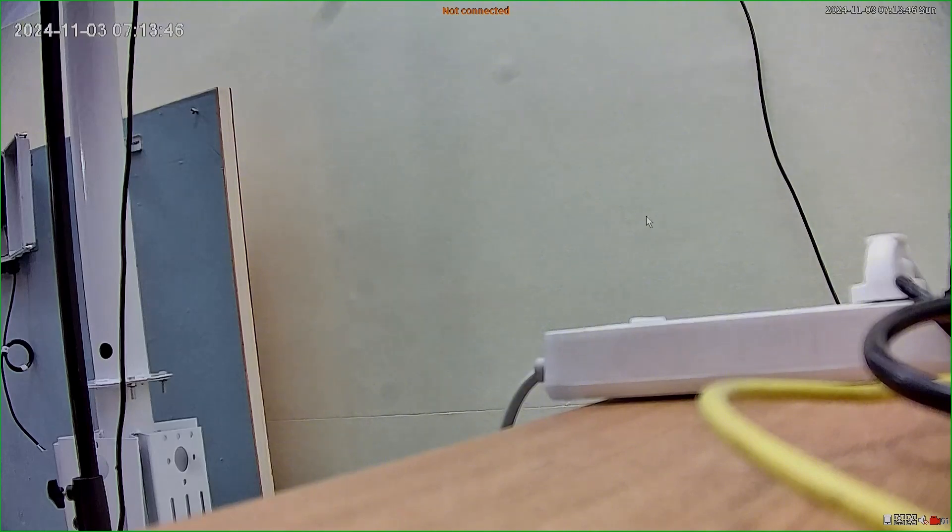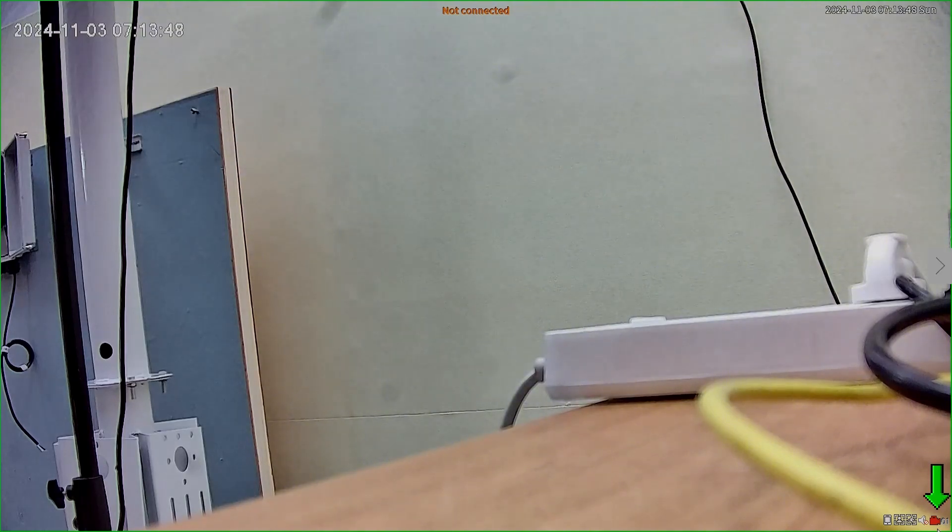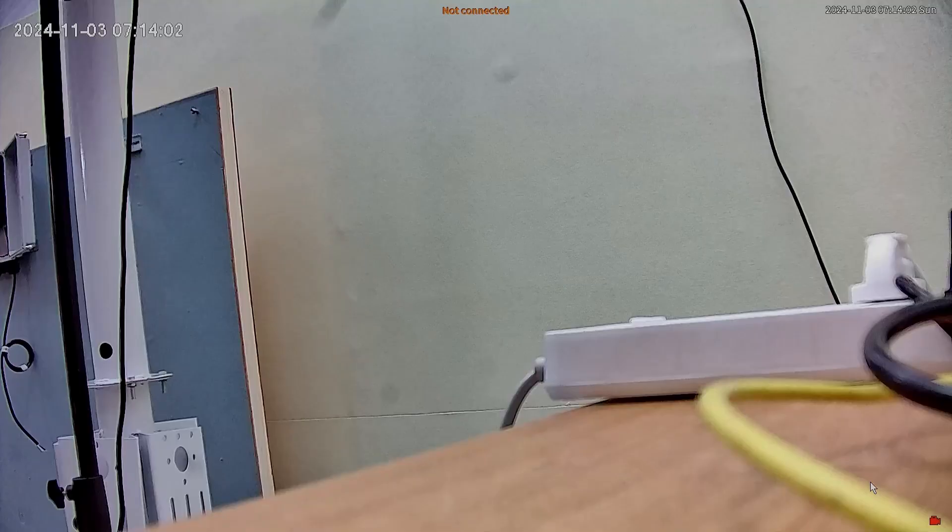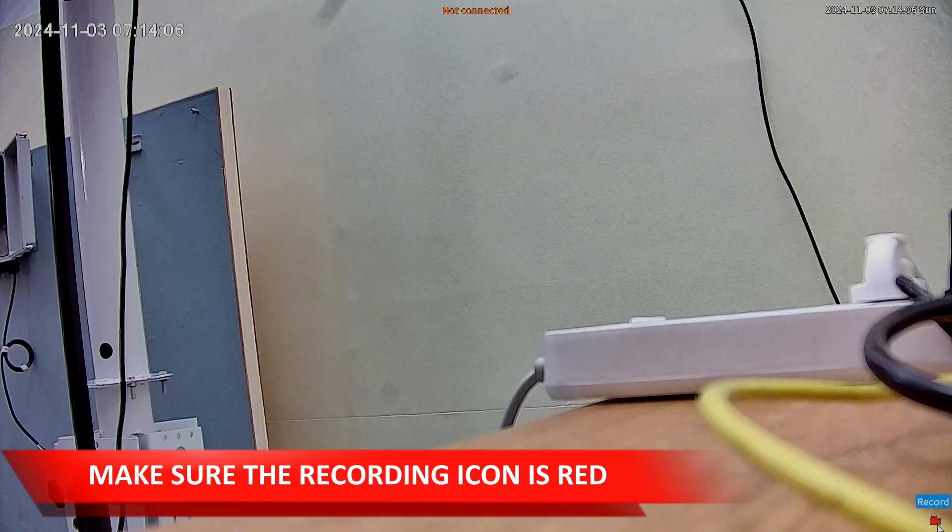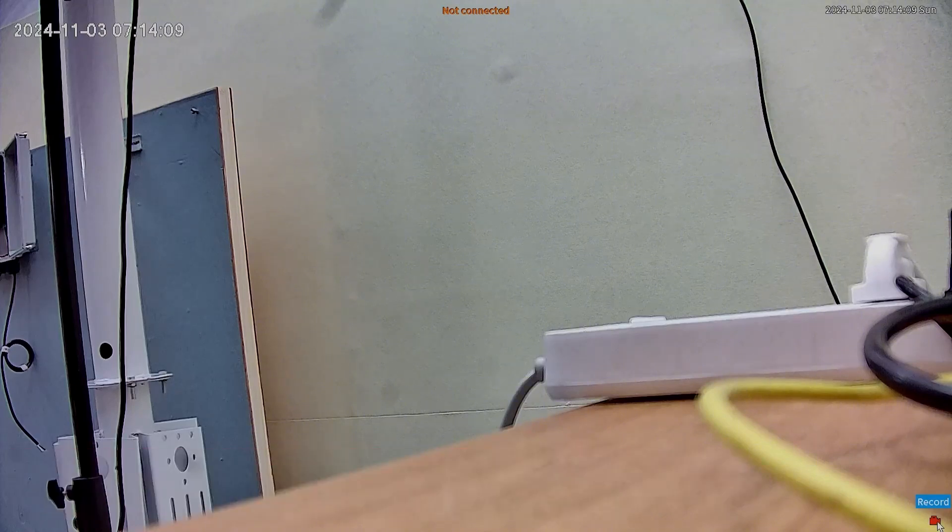One thing important is this red icon. Remember I said, even if you don't install the hard drive to your network video recorder, you still will see the live video on the monitor. So seeing the live video on your monitor doesn't guarantee the network video recorder is recording. It's better to go back to check this recording button. Make sure it's red. We have complete all the settings.